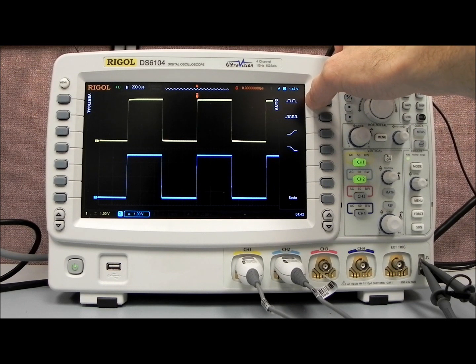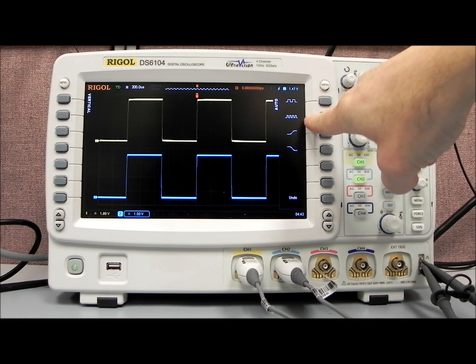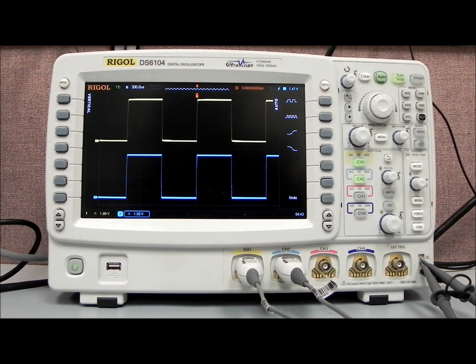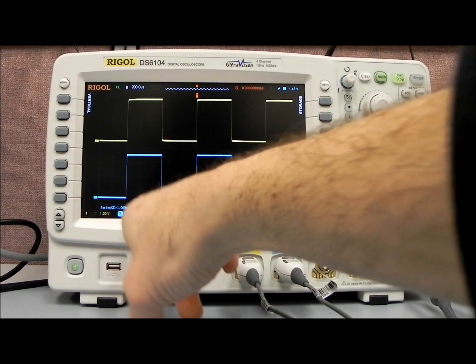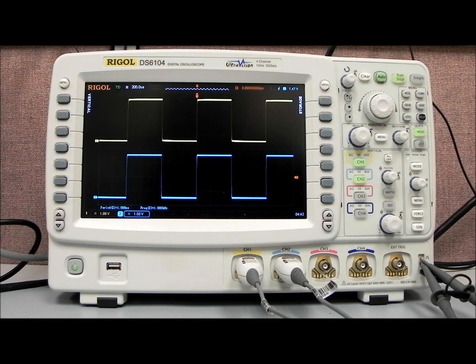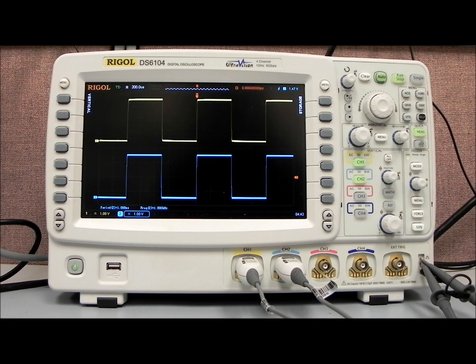We can select small sets of waveforms or large sets of waveforms, and that's really just the number of periods we're seeing on the display. We can go to a rising edge or falling edge, and that's just going to select one of the rising edges or falling edges for more analysis. I'm going to select a smaller set, and now you'll see channel 2 is highlighted. It's also brought up automatically two readings for the period and the frequency of channel 2. Channel 2 was connected to that probe compensation point, and that is a 1 kilohertz signal. You can see here we are reading 1 kilohertz as our frequency readback.